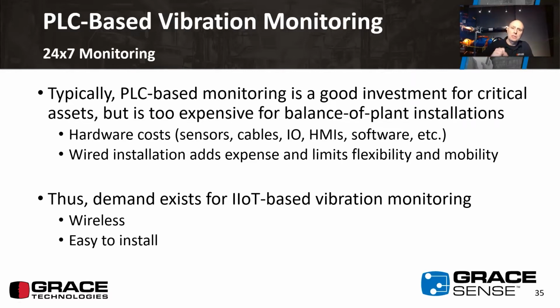The problem with these PLC-based methods is that they're too expensive in most cases for balance of plant installations. That's driven by hardware cost - sensors are expensive to start, but when you add cables, I/O, PLCs to capture the information, display it on HMI, and buy software, it adds up. A wired, tethered installation, typical for going into a PLC, adds expense just from running conduit and all the typical things that go with a wired installation in an industrial environment.